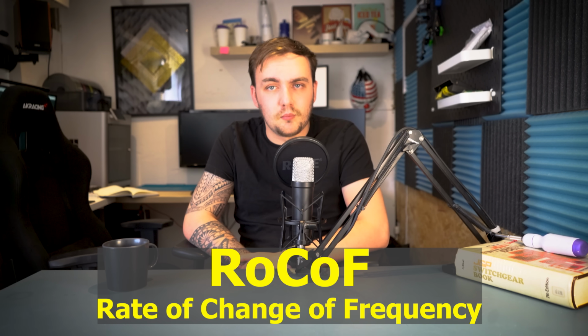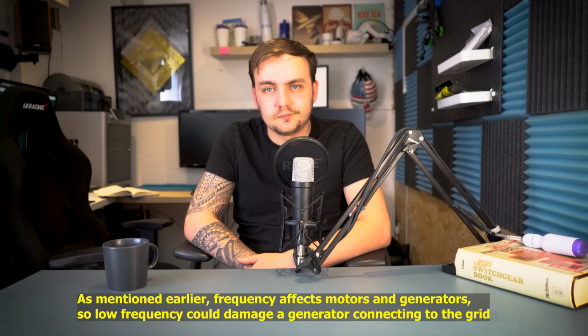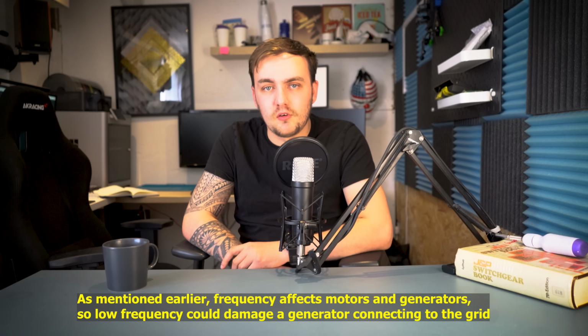If the frequency begins to drop too quickly, say faster than 1 Hz per second, RoCoF protection can kick in to disconnect sensitive generators or prevent new ones from connecting, to avoid instability or damage. This is especially important for renewables and inverter-based systems, which don't tolerate fast frequency swings like big spinning turbines do. The faster the RoCoF, the less time operators have to respond, which is why inertia from synchronous machines is still so valuable. It slows the rate of change and buys critical seconds for other responses to kick in.